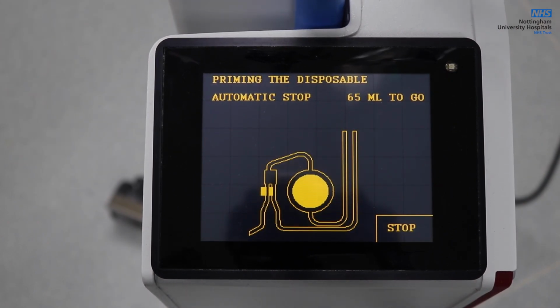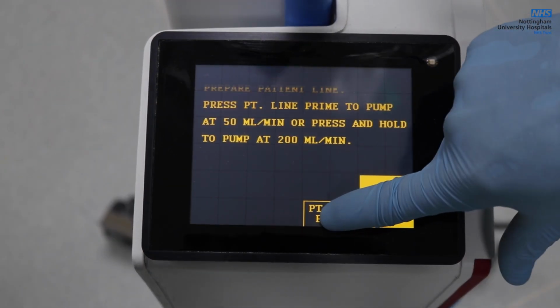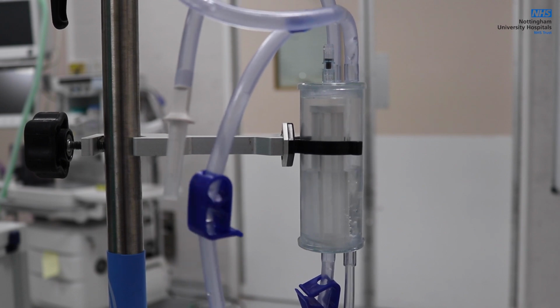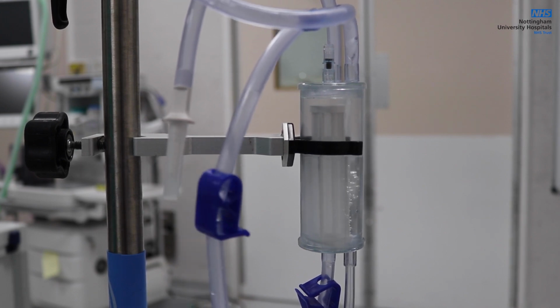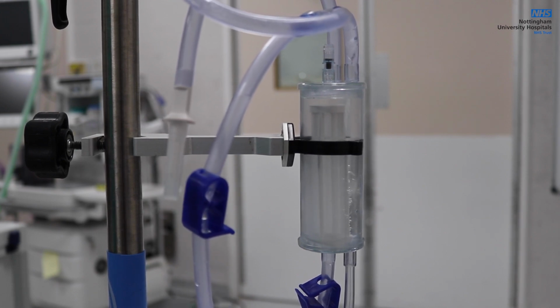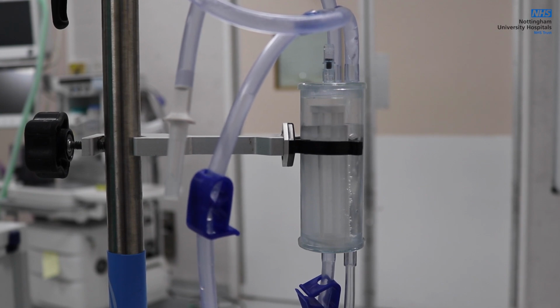Once primed, please document on monitoring sticker who has primed the device, date and the time in order to track and trace, allowing the reviewing and monitoring of preparation of the device. Priming must be with sodium chloride 0.9%. Do not prime with Hartmann's as this cannot mix with the blood.